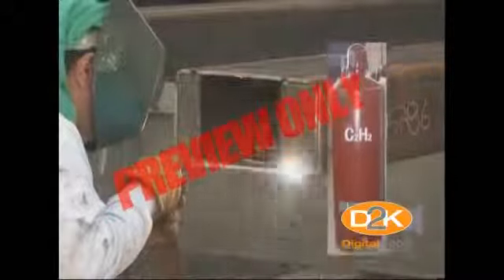Cylinders containing flammable gases such as hydrogen or acetylene must not be stored in close proximity to open flames, areas where electrical sparks are generated, or where other sources of ignition may be present. Cylinders containing acetylene must never be stored on their side, as the contents may leak out.